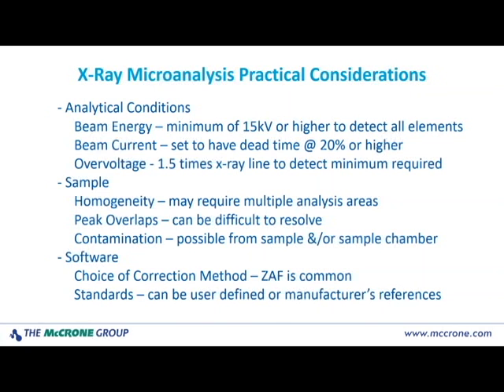Your software will have some options available to you, one of which is the correction method you're going to use to convert your qualitative analysis to your quantitative analysis. One of the routines that's often available is called ZAF. The Z stands for a correction for the atomic number, which element is present in your sample. The A is the absorption — how many of the x-rays are being absorbed and lost. F is fluorescence — you're getting secondary fluorescence coming out, maybe from another element. You also have the option in your software to use the manufacturer references to convert your data from qualitative to quantitative, or you may want to set up and define your own standards. It's a complicated process and probably not something the beginner wants to take on right away.